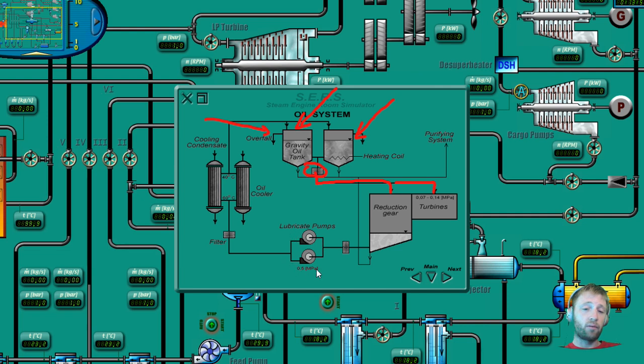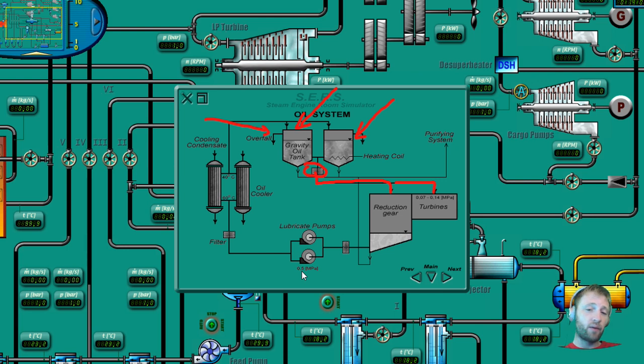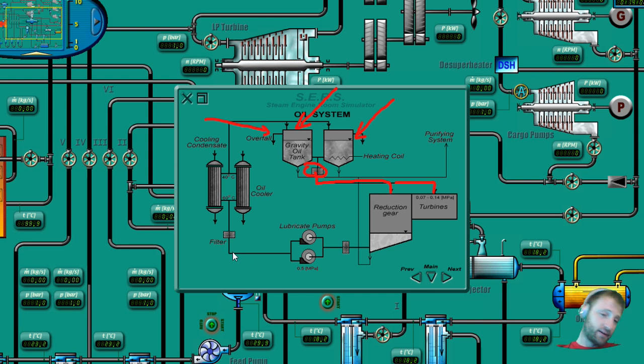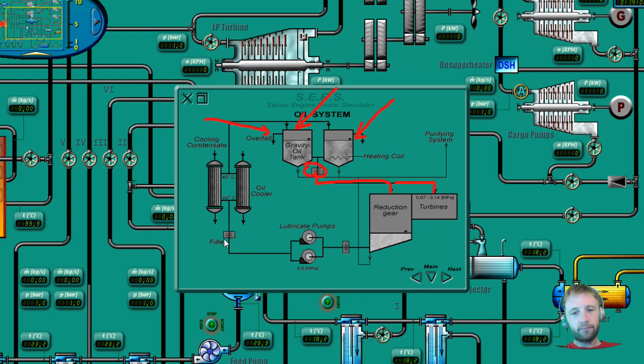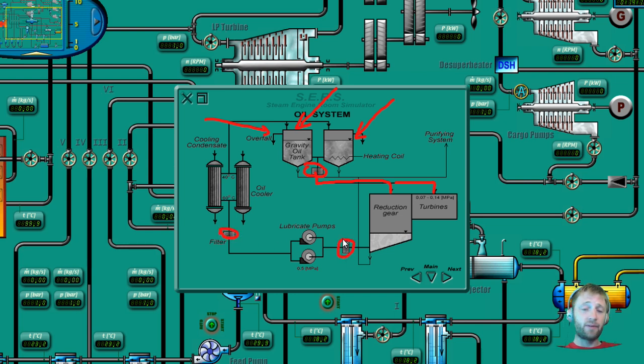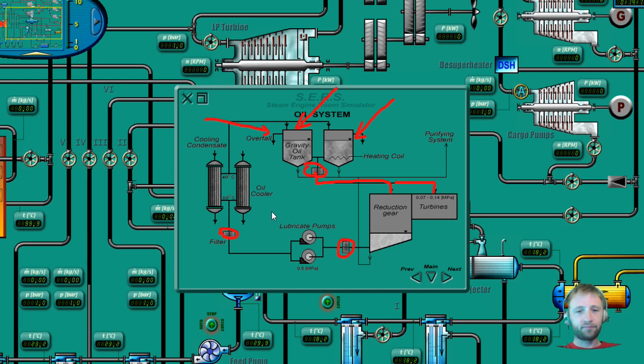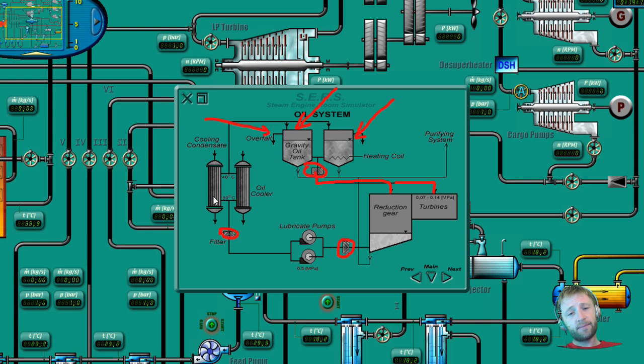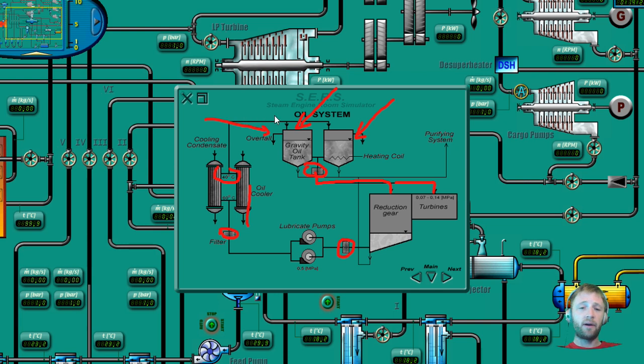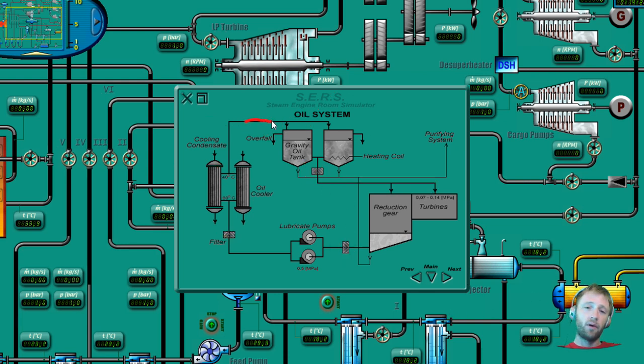After that, from here when the lubricating oil finish its work, the oil is passing again some filters to protect our pumps here and clean also. These pumps supply with pressure of 0.5 MPa, and then passing some filters again. As you can see, there's a lot of filters because the oil must be as much fine as possible. After that, from 60 degrees the oil cools down to 40 degrees and again return to the system back here. So this is the cycle of the oil.